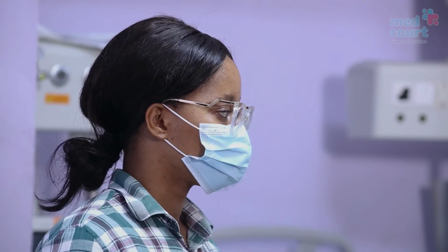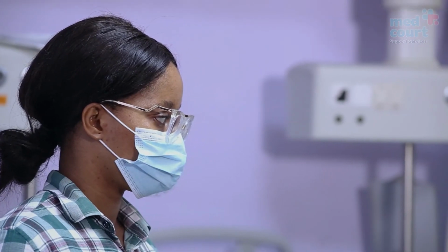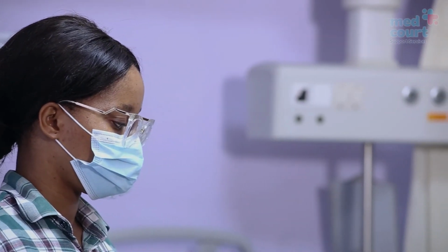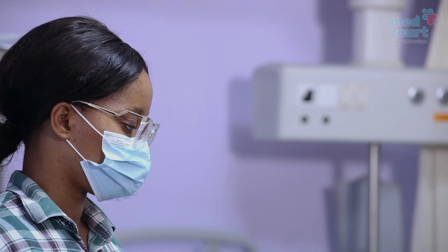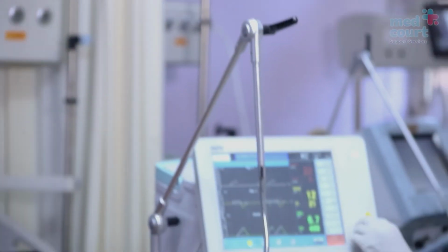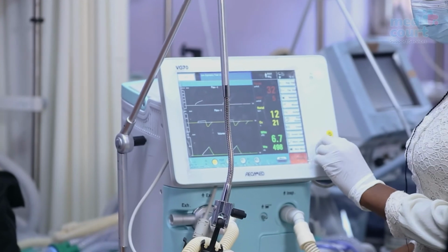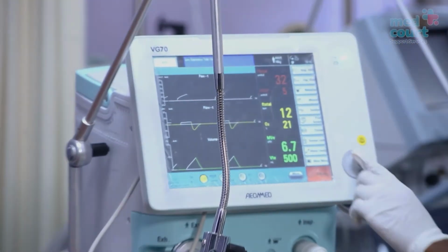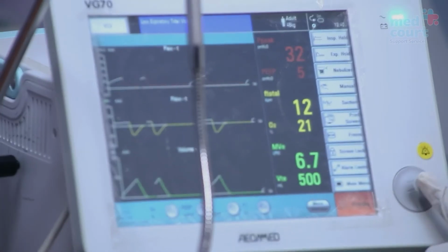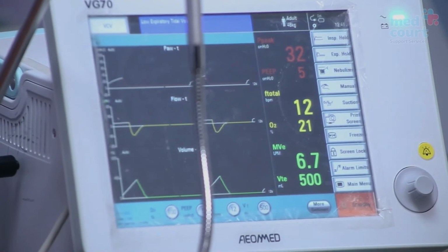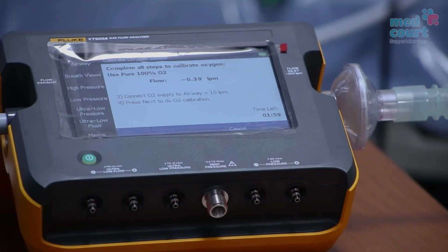So on the ventilator, we click the O2 percentage and set to 100% oxygen. Then we enter. Click Next on the VT900A. Calibration takes 2 minutes.